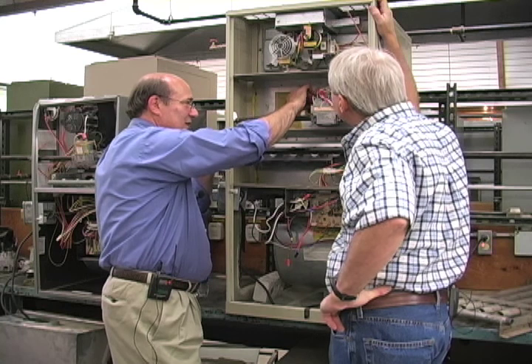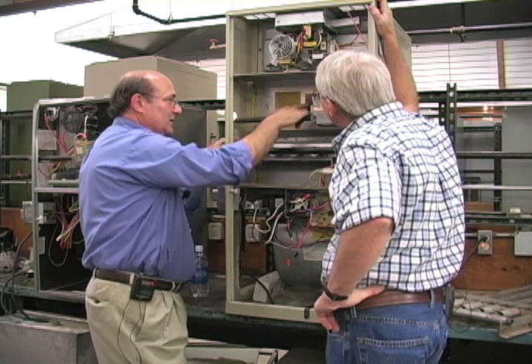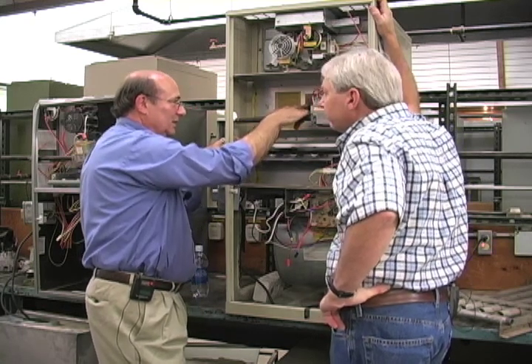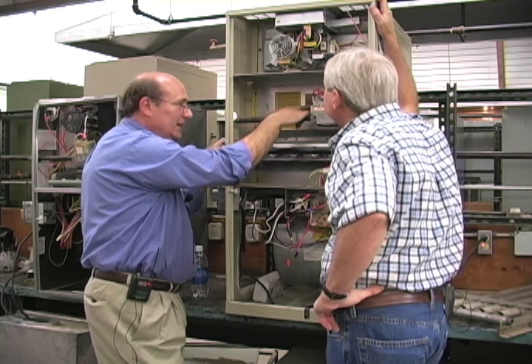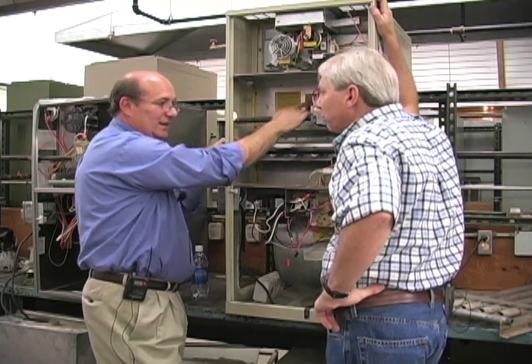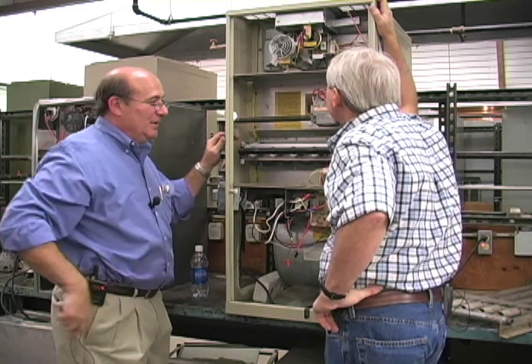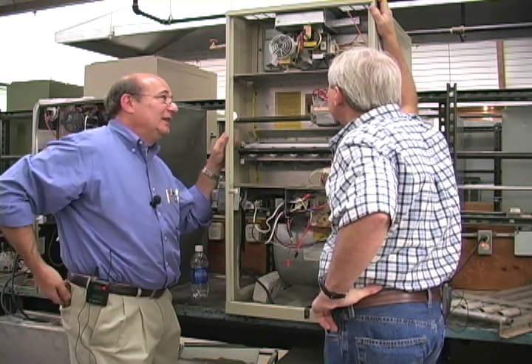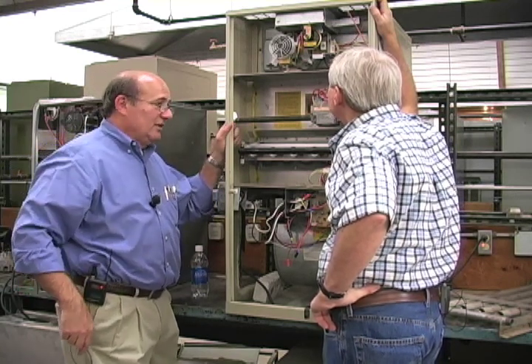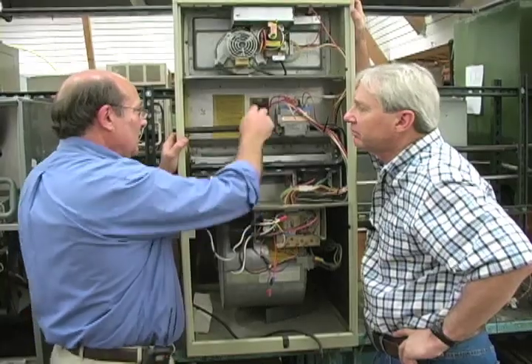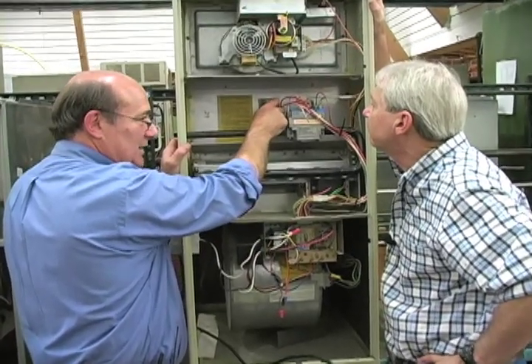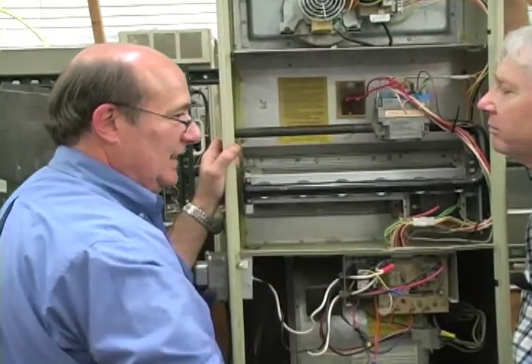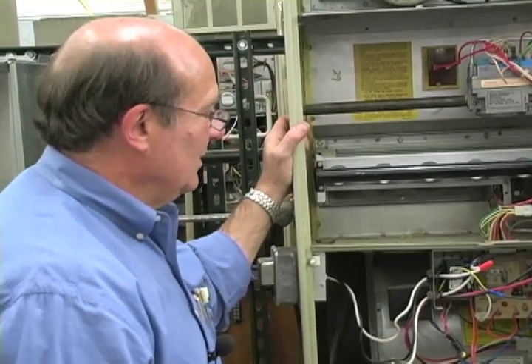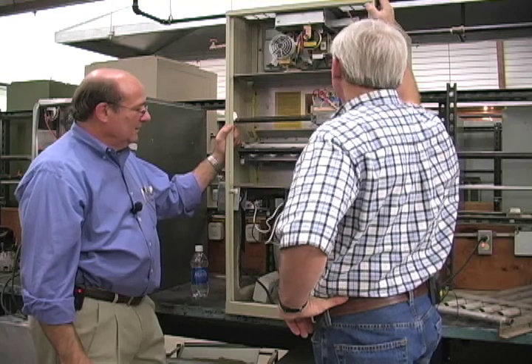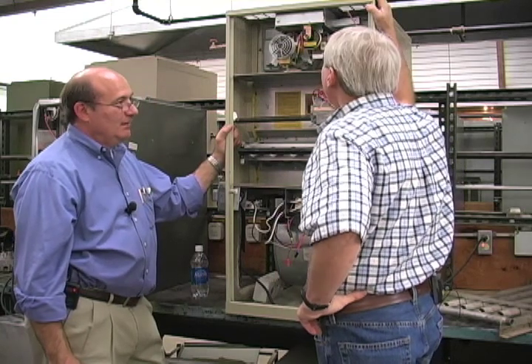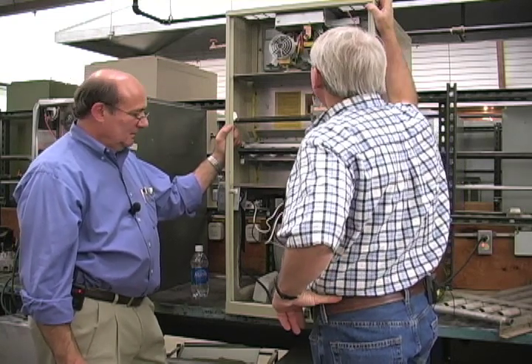If you go to a limit switch like this and you see the plastic connector is melted, or wires charred back in here, brittle, I'd say you might have had some problem in the past. Maybe it's fixed by now, but if I was servicing your furnace and I found that, I would take that old wire, cut it back to where it's not charred, put a new connector on it, and I'd have a nice brand new system. So if we see signs of overheating, that's when we recommend service. You bet.